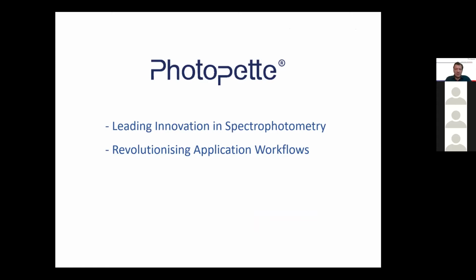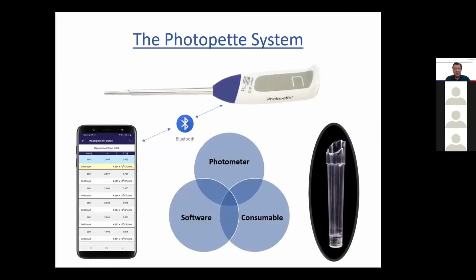What is a Photopette? The Photopette is a handheld spectrophotometer, and it has a very different workflow and certain unique applications. The Photopette is actually a closed system. So it's different to the standard benchtop spectrophotometer that you may have in your lab, where you can use different types of cuvettes from different manufacturers and so on. The Photopette is a system built from 3 components: the Photopette device, then the Photopette software, which runs on a smart device like a tablet or a smartphone on either Android or iOS, and the Photopette cuvette tip, which is a disposable that is basically replacing the classical cuvette. So those 3 components form a closed system.